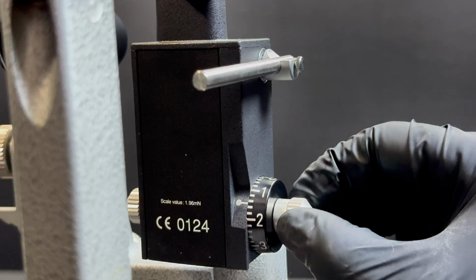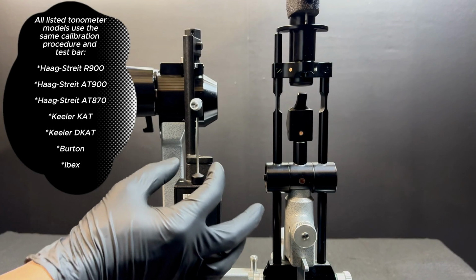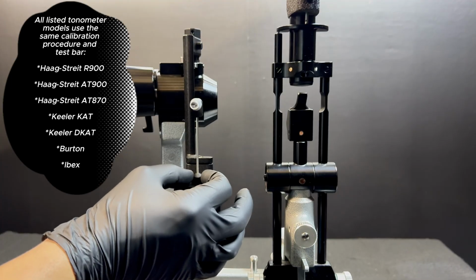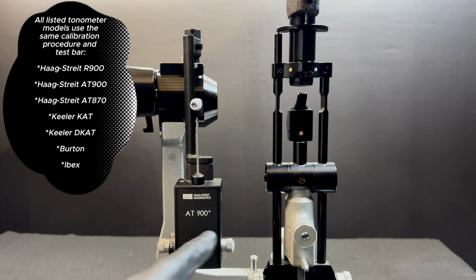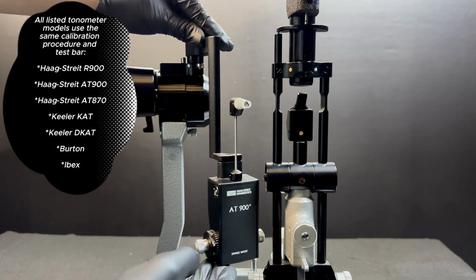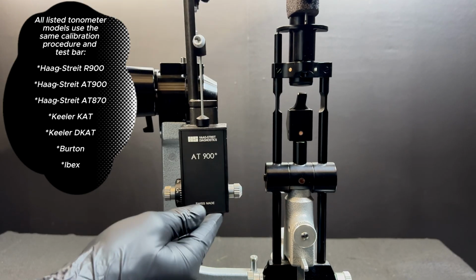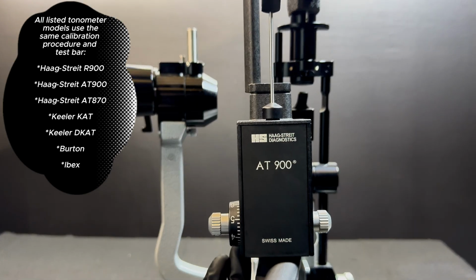In this video, we'll show you how to check the calibration on your tonometer. Tonometers contain small, precision mechanical parts, including the feeler arm and internal bearings. If the instrument is bumped, dropped, transported, or removed from the slit lamp, calibration must be rechecked.